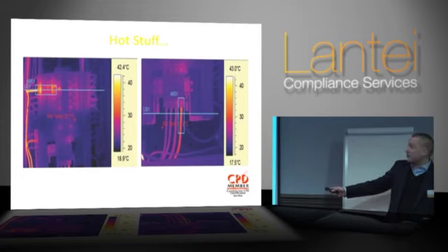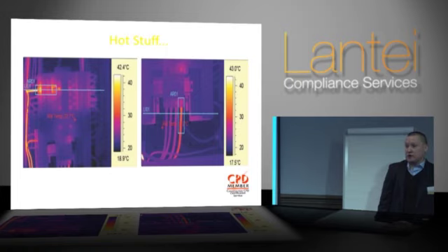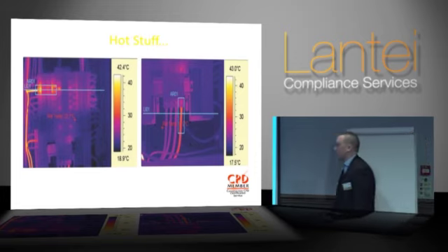Going into the isolator, that very warm cable on the right is a neutral conductor suffering from harmonic distortion issues. That's the effect harmonics can have. Very, very real, ladies and gents, very real.